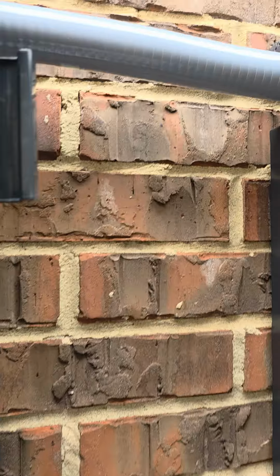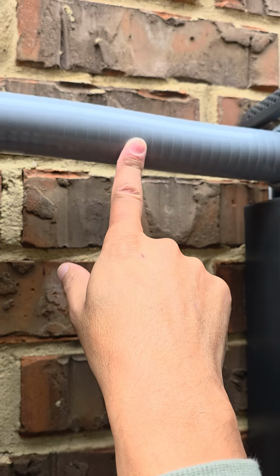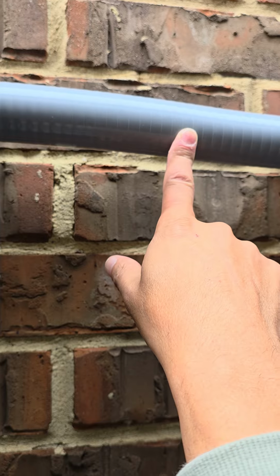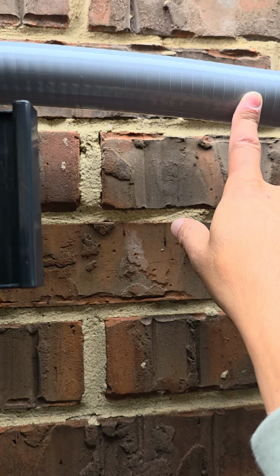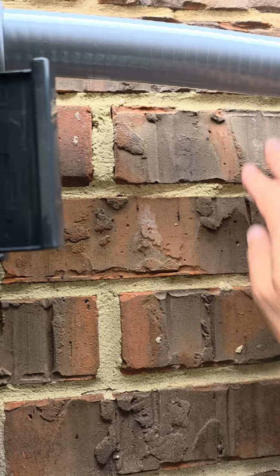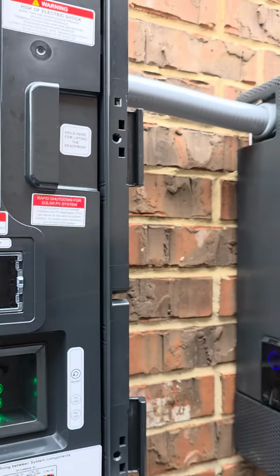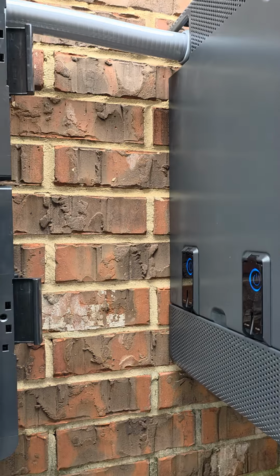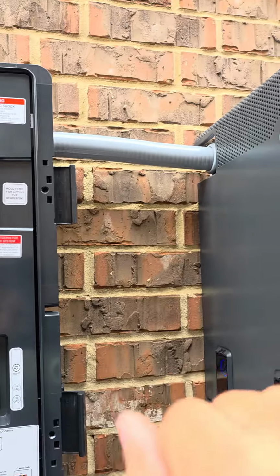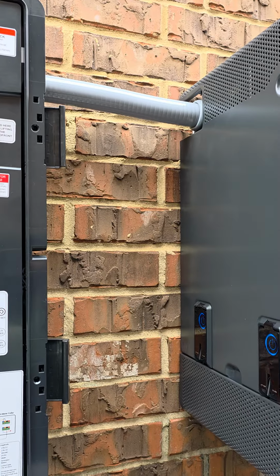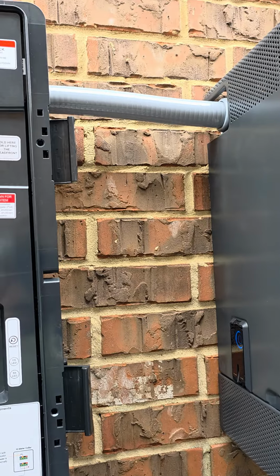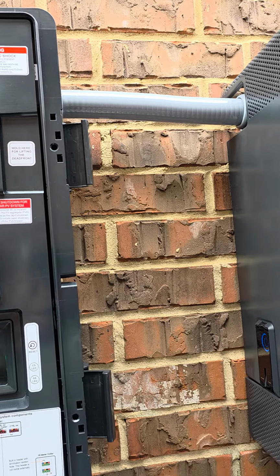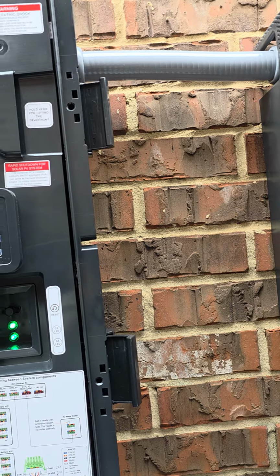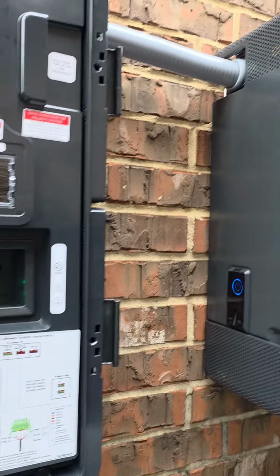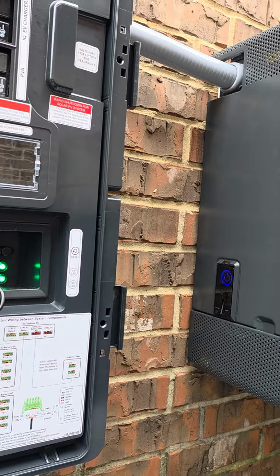But anyways, moving on. I will say when you're installing the batteries, using this flexible non-metallic conduit is huge. I can't imagine once the wall side battery is installed how you could do rigid conduit. Again, I'm not a professional installer. I'm sure there's an easy way to do it that I couldn't think of, by maybe sliding the rigid conduit back and forth to get the collars on and getting it installed. But for me, being able just to basically bend the conduit down and up to get it installed on either side was way easier than doing rigid.